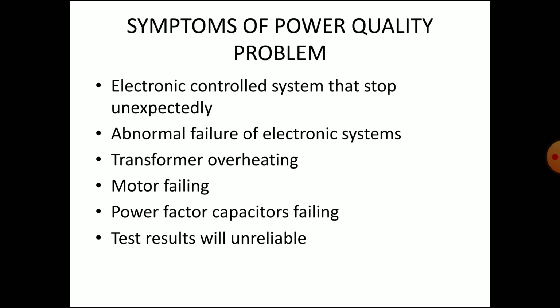So what are the symptoms of a power quality problem? How can one define that the system is being fed with poor power quality? That is, an electronically controlled system that stops unexpectedly. Suddenly, connected sensitive electronic equipment will stop functioning. Abnormal failure of the electronic system. Transformer overheating, meaning core heating, motor failing, power factor capacitors failing, and the test results will be unreliable. So if something related to these points happens, then one can say that the system has a poor power quality input.